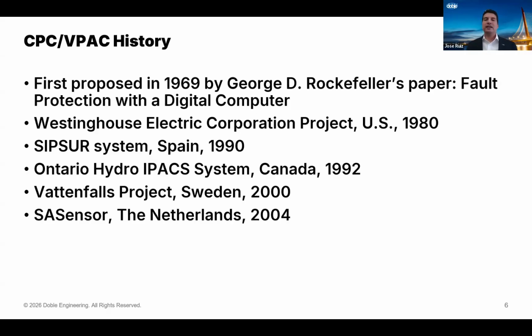Then we have the Vattenfall distribution. So in collaboration with ABB, this utility company developed a CPC system for the island of Gotland. All protection and control algorithms use a real-time kernel with an embedded Windows operating system. This basically runs on a standard industrial computer, and it connects to 5 racks for analog inputs and outputs. Basically, the signals were gathered to the centralized unit for the protection purpose.